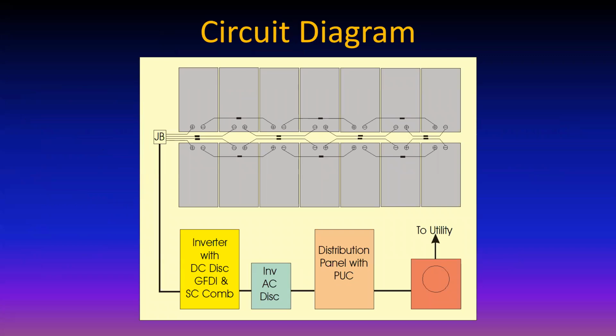So here's our design of our circuit. And notice I did this on purpose because the module manufacturers, if you're just connecting straight grid connect, are pretty smart in terms of how long they make their leads on the module. You can see that I can skip over one module there from the upper left to the third one in from the upper left. I can connect a minus to a plus, and then I can hop over another module and hop over another module. And most of the wiring is just the module wiring that's already built in on the modules, and just a couple little extensions at the end going to the junction box for these two strings.